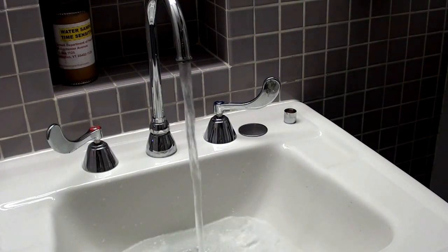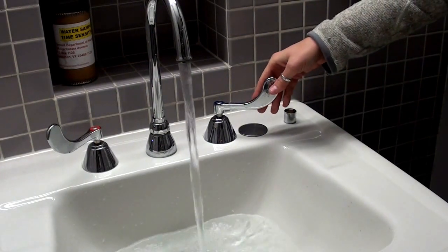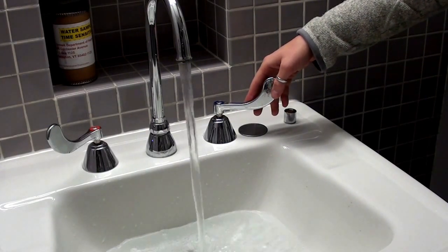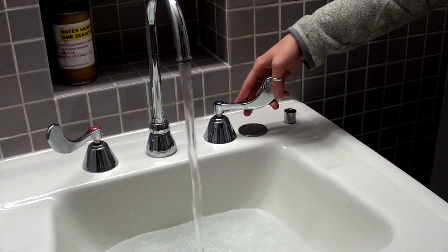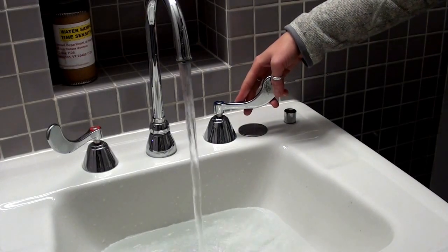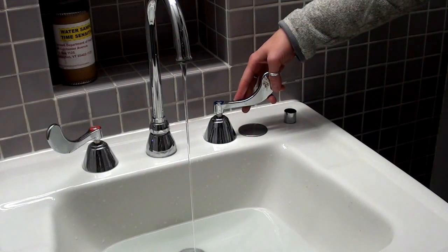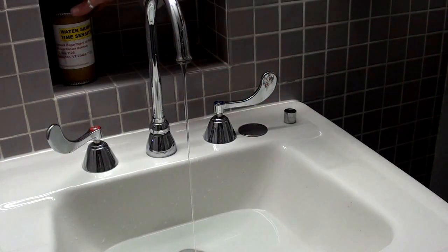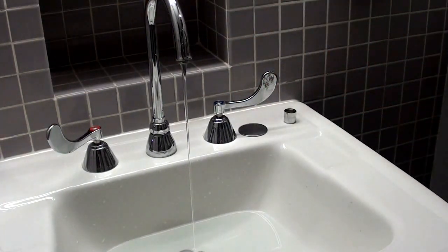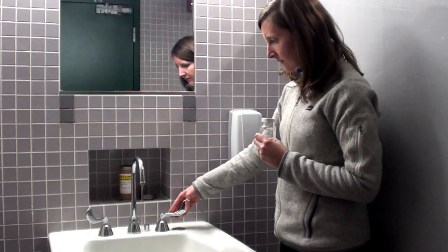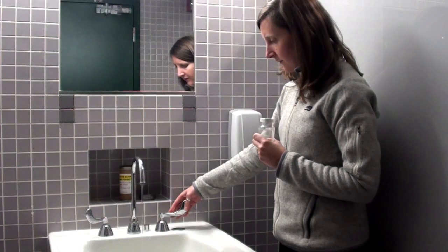The operator will perform a visual inspection of the sample taps that produce the total coliform positive sample results. If, while taking the samples, the operator used a less than ideal tap, it could yield a total coliform positive result. The division encourages that systems use a non-swivel faucet with separate hot and cold valves that are either smooth nose or that have removable aerators and external threads.